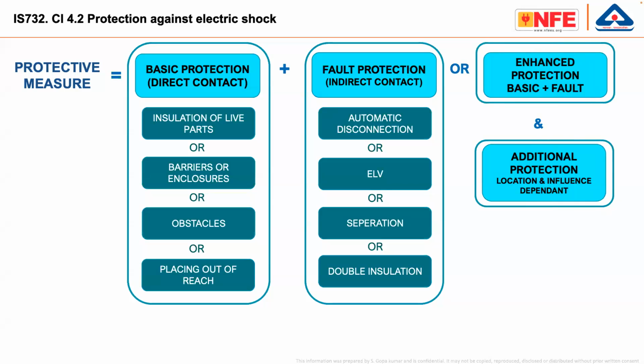Sometimes for some parts of the electrical installation, even if basic and fault protective measures are available, additional protection measures are necessary depending upon the location and the external influence. Say, for example, we are using some handheld class 1 electrical appliance. In that case, for a normal person, it is a better idea to put an additional protective measure. Additional protective measures are supplementary equipotential bonding, use of 30 milliampere RCD, and so on.